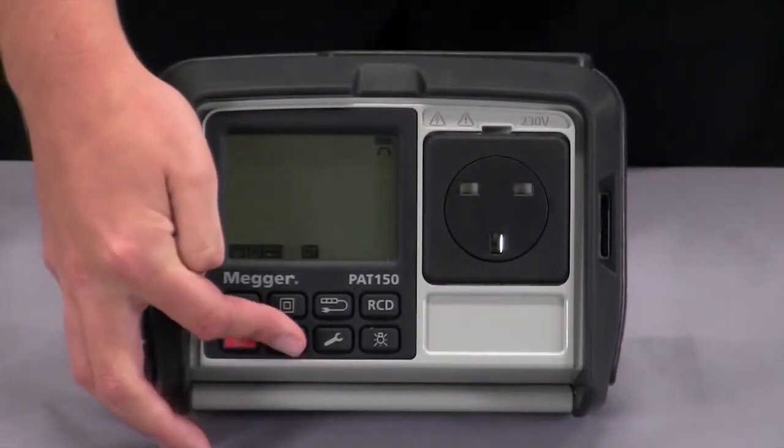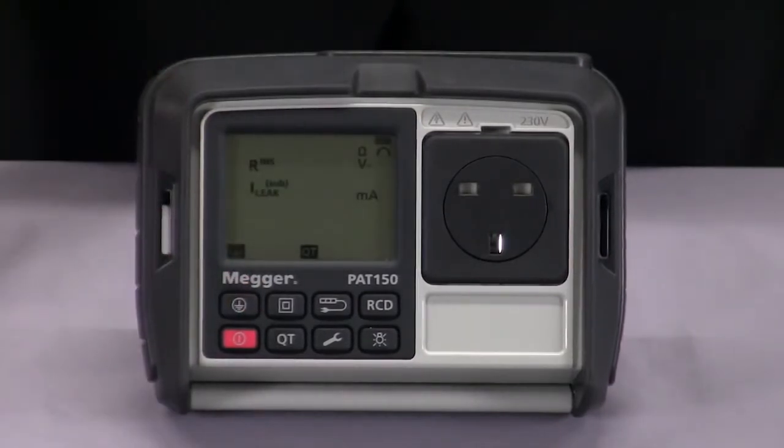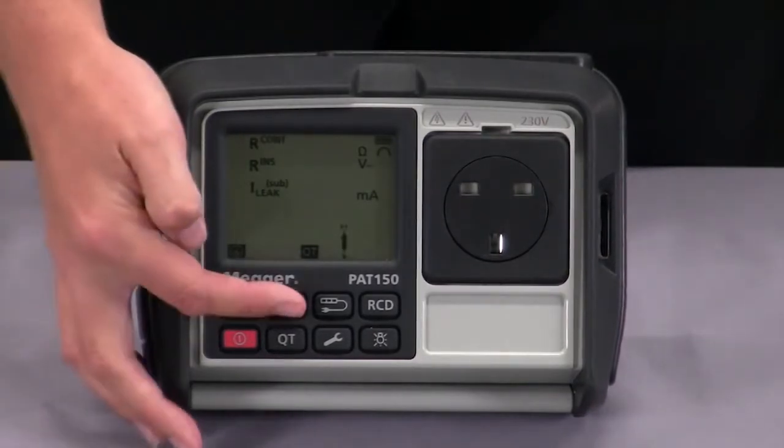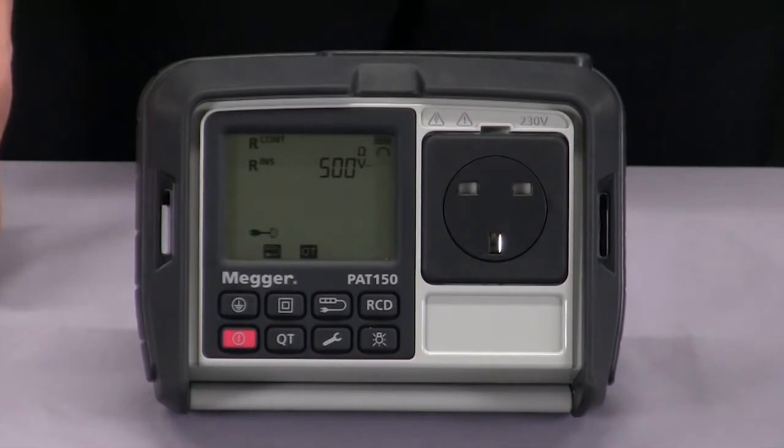Pressing the QT button takes us into the quick test mode. We can then select the class 1 button which gives us the option of choosing a continuity test, insulation resistance at 250 or 500 volts, a substitute leakage test, or if you've got mains connected, the mains leakage test. Pressing the class 2 button will allow us to choose an insulation test at 250 or 500 volts, the substitute leakage test, a mains leakage test if you have the supply connected, or SELV measurement — the separated extra low voltage. Extension lead options include the continuity test, insulation resistance at 250 or 500 volts and also the polarity check.